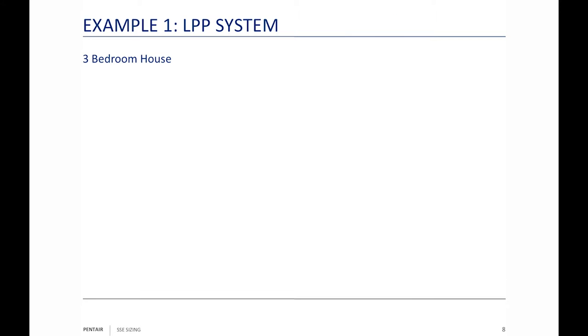In Example 1 — and if you have the SSE training manual, we're on page 34 — we've got a three-bedroom house. Most local codes say 150 gallons per day per bedroom. I have to word it that way because I'm speaking in generalities. Generally speaking it's 150 gallons per day per bedroom, but you have to know your local codes and follow them, because if your local codes are different it could cause a problem.